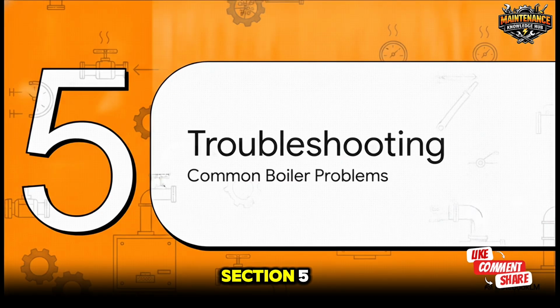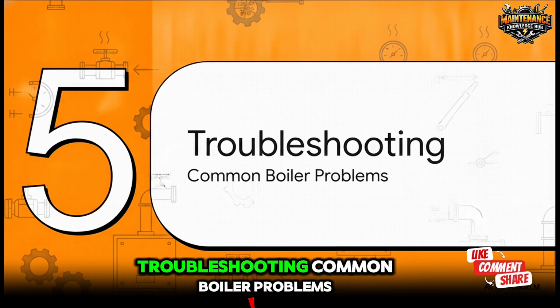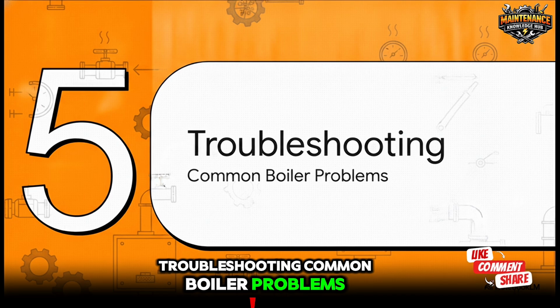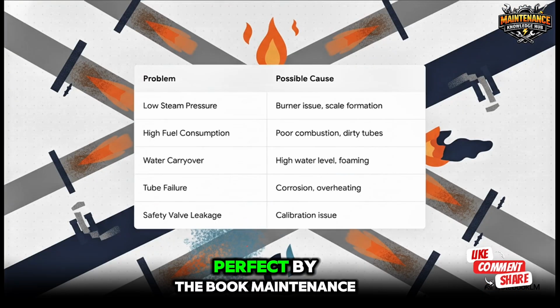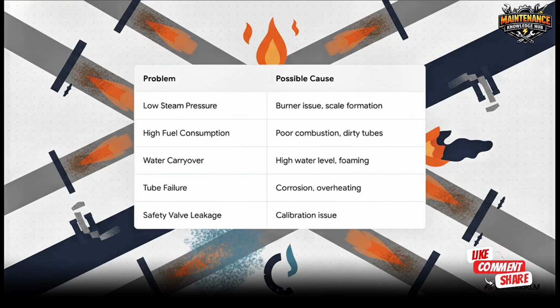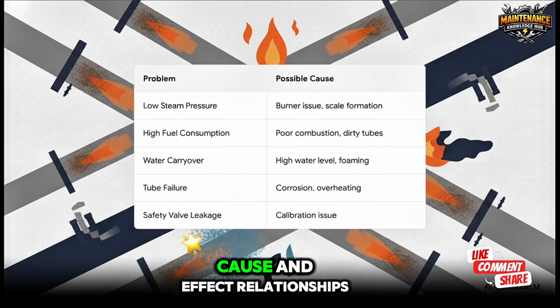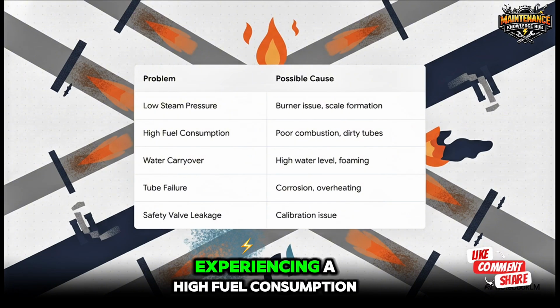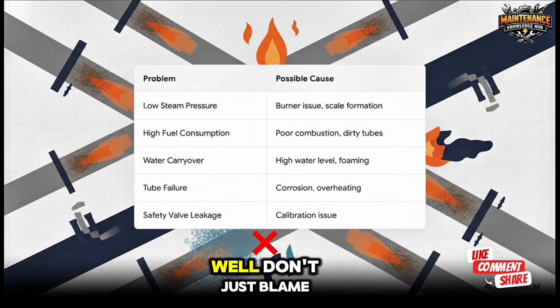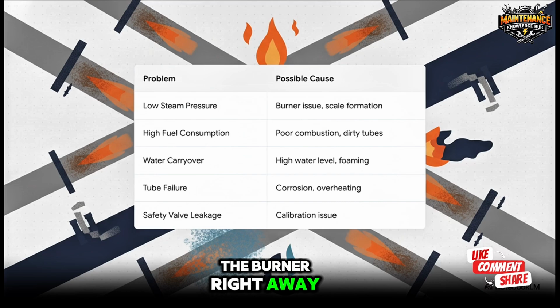Which brings us to Section 5, Troubleshooting Common Boiler Problems. Because look, even with perfect, by-the-book maintenance, things are inevitably going to start acting up on the plant floor. When they do, you really have to understand the direct cause and effect relationships at play. Experiencing high fuel consumption? Well, don't just blame the burner right away. Check for dirty tubes causing poor heat transfer.